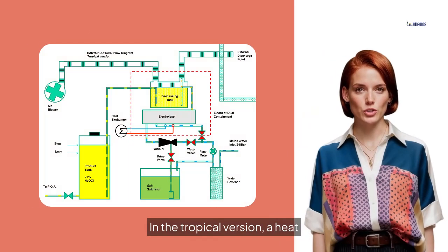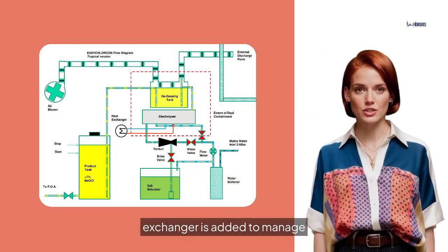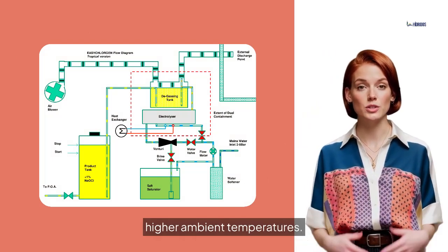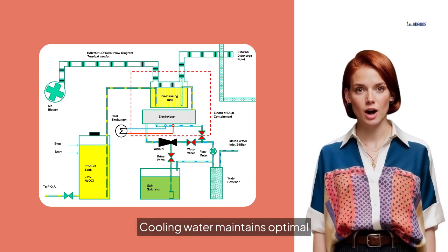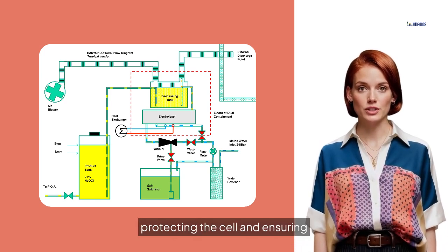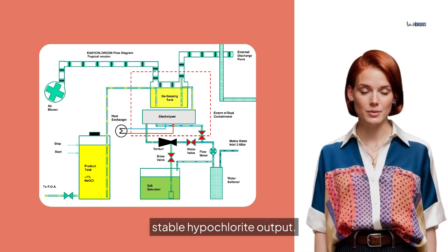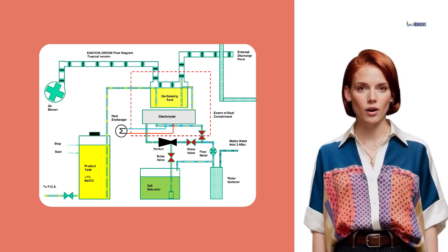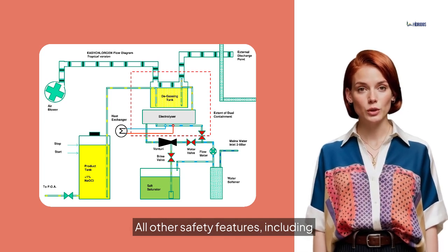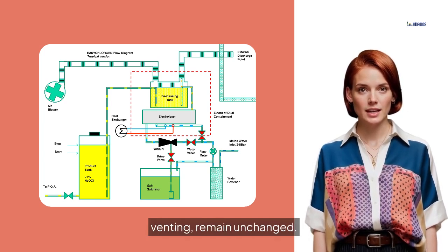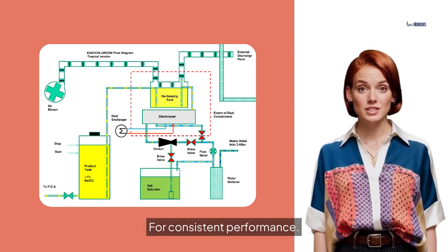In the tropical version, a heat exchanger is added to manage higher ambient temperatures. Cooling water maintains optimal electrolyzer temperature, protecting the cell and ensuring stable hypochlorite output. All other safety features, including dual containment and controlled venting, remain unchanged for consistent performance.